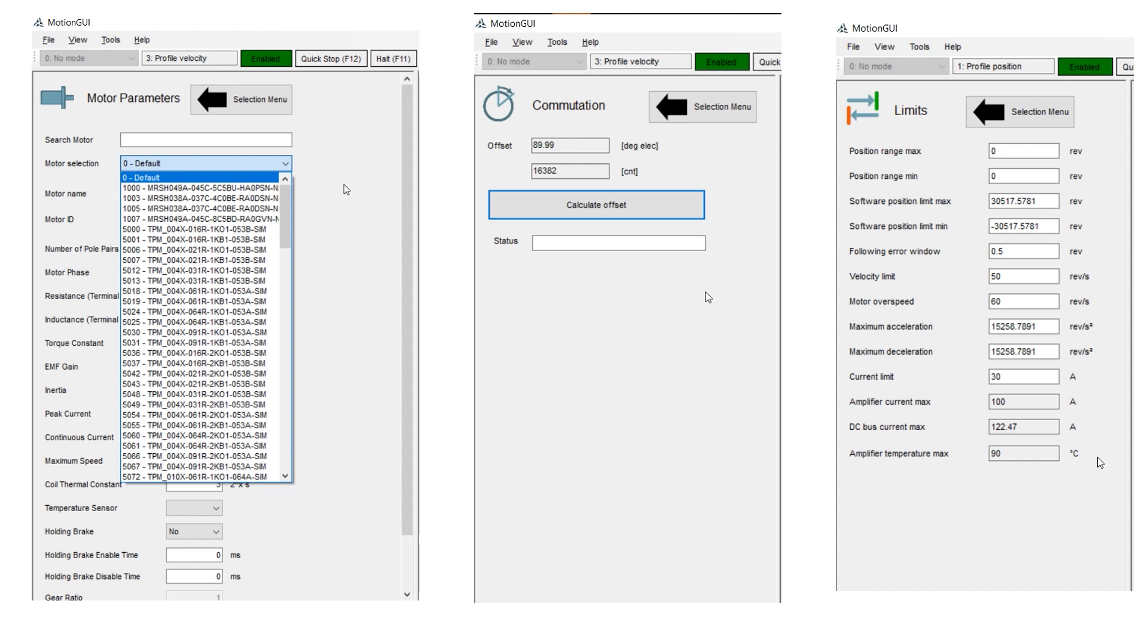Under Motor Parameters, you can select a Wittenstein catalog part number, or if using a third-party motor, directly enter the nameplate data. Once that is done, you'll need to click Commutation and Calculate Offset to set up motor commutation.